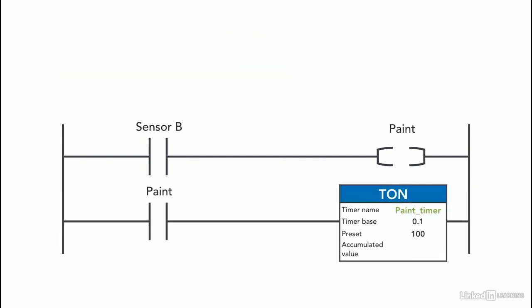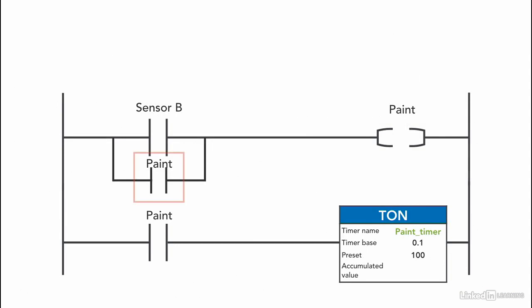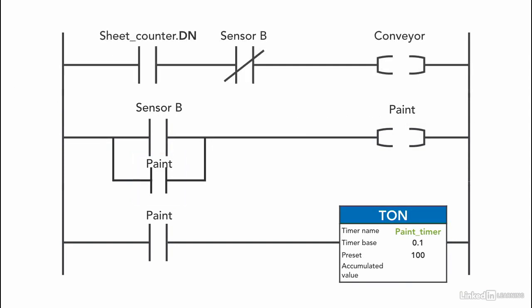The paint is applied for 10 seconds, so we need to add a timer on delay to keep track of the time. If we select the timer base as 0.1, then the preset value is 100. In order to keep the paint on, we're going to use a hold-in or seal-in instruction to keep the paint on during that time. This is how the program looks so far.